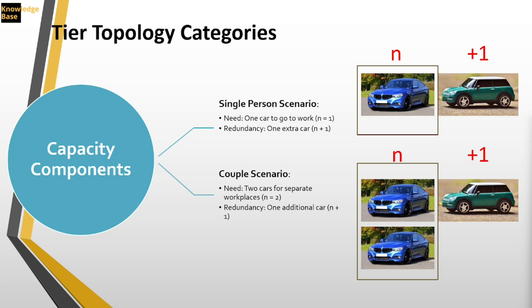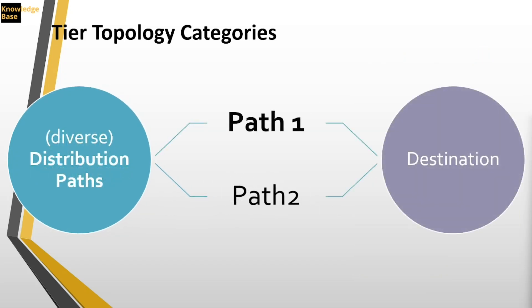Now let's look at path diversity. We have the capacity component, and path diversity means the way I want to deliver power should go through two different paths. If I have a single power panel where two UPS systems meet, that's a single path — I lose the redundancy in the path and don't have path diversity. These two topology categories define the data center tier level.